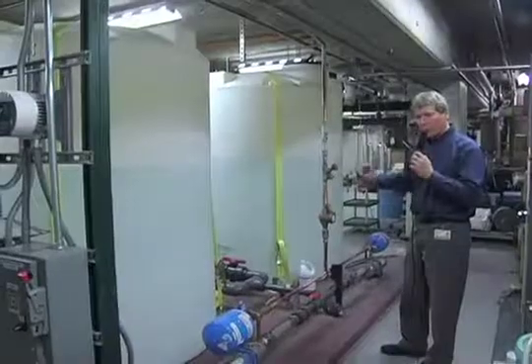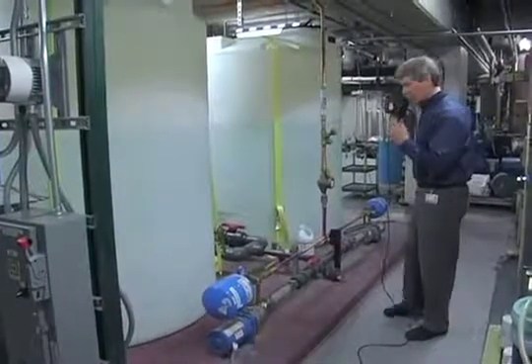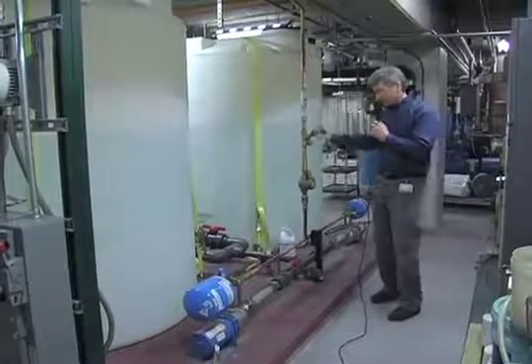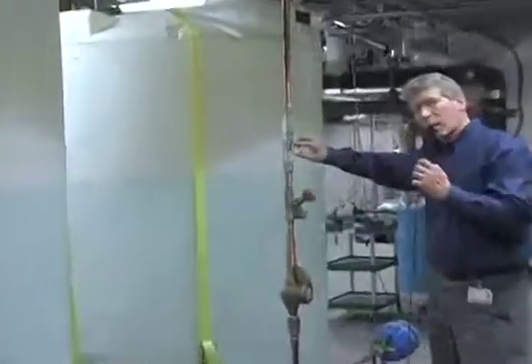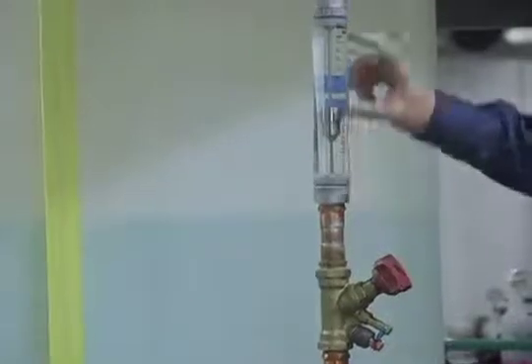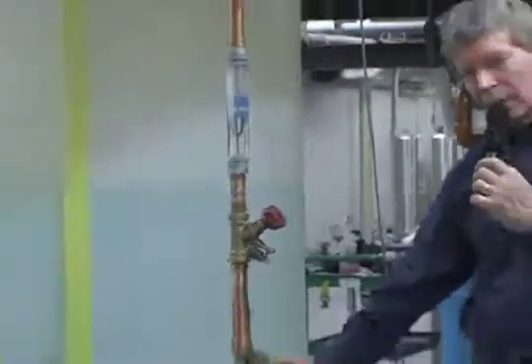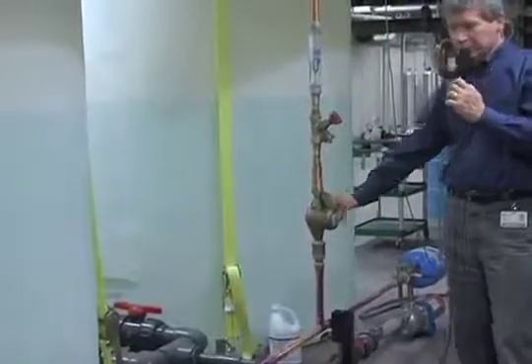They pump the water up at about 60 pounds pressure up to this water pre-wash station. And note that we have instrumentation here such as flow control valves. We have a rotometer so that we know how many GPM we have going at any time, and this does fluctuate. We also have a water meter here that tells us how much water that we're using every day.